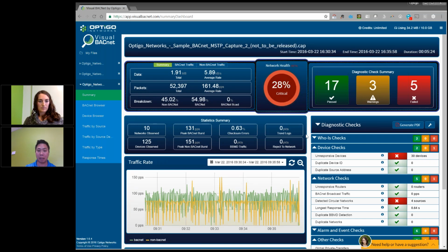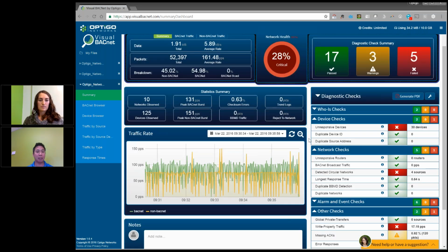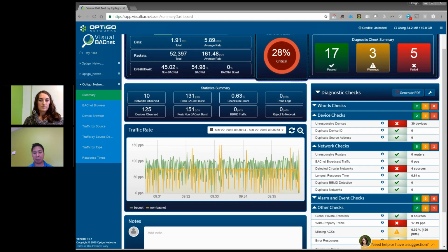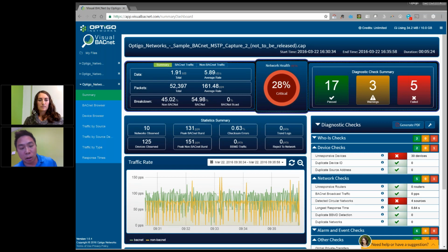This is an MSTP capture, and just so you know, in MSTP the non-BACnet frames are basically your tokens. Any non-BACnet frames are deemed non-BACnet. So in this case, about 55% is BACnet and 45% are tokens and requests for polling, requests for master, things like that.